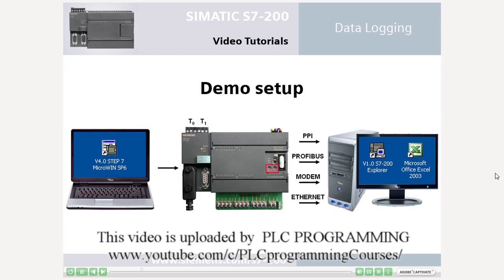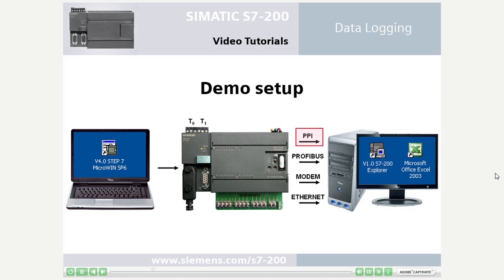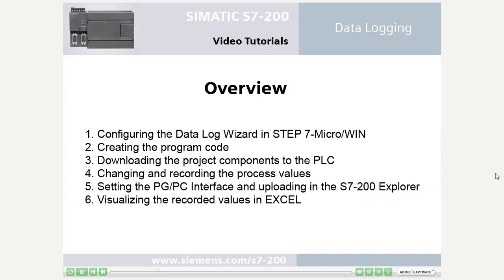The temperatures are simulated by the analog adjustment potentiometers of the S7-200 PLC. The recording is activated by input 0.0. Finally, the recorded process data are read out in the S7-200 Explorer through a USB PPI cable and visualized in Microsoft Excel. The task includes the six steps described below.